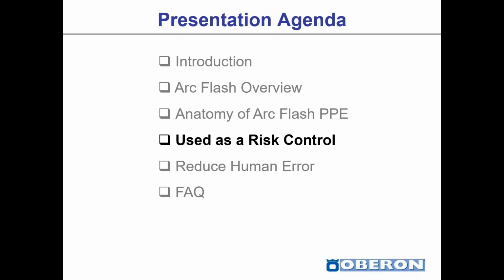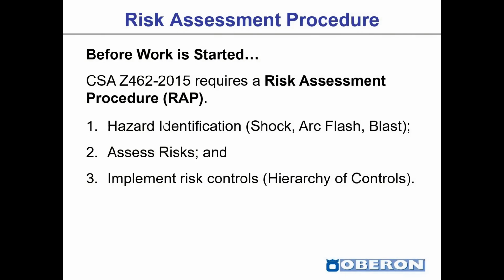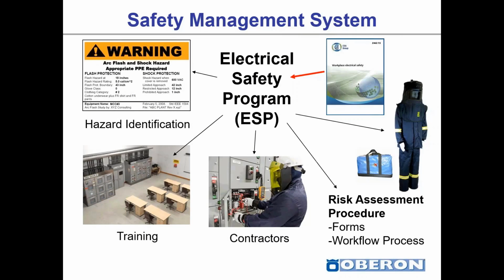So moving on in the presentation, arc flash PPE is used as a risk control. Essentially, before work is started, the applicable standard requires a risk assessment procedure to be completed, and that breaks down into hazard identification. Examples would be shock, arc flash, and blast. Assess the risks, and then implement the risk controls using a hierarchy of controls. Now that hierarchy of controls would have arc flash PPE as the last line of defense. It is, however, the most readily available and commonly used control to mitigate the risk. Risk is a combination of severity and likelihood as defined by NFPA and CSA standards. So we look at the severity as being the potential arc flash or thermal energy measured as incident energy. And then the likelihood is where we rely on your safety related work practices, your safety management system. So an electrical safety program helps in terms of identifying the likelihood of an arc flash occurring.